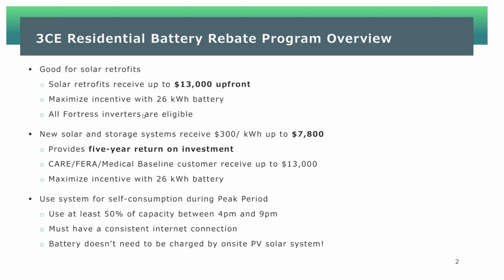So that's how I'm coming to these numbers of this 5-year investment, because you can use lithium batteries now in a way that you can cycle them once a day and maybe even double cycle them once a day, just because of how far the technology has come, right? These are not lead acid batteries. We actually encourage you to use your battery, and using it in these sort of programs can give you huge financial incentives, a huge financial break when looking at your investment for solar and storage. So 3CE is a very exciting one.